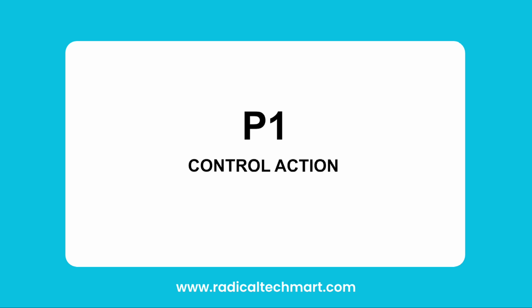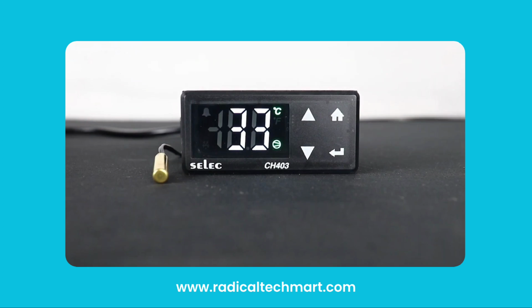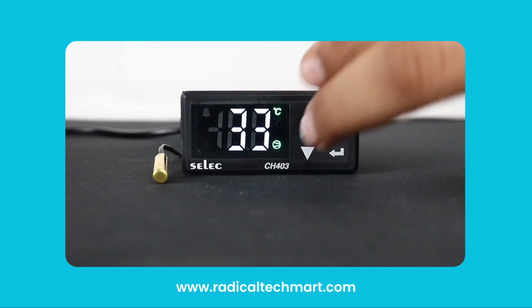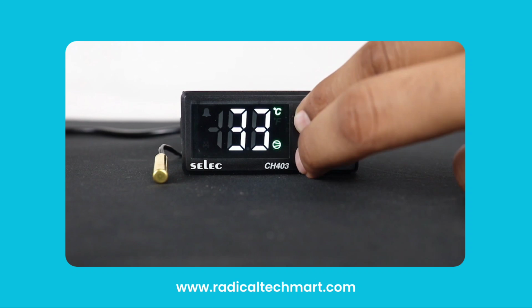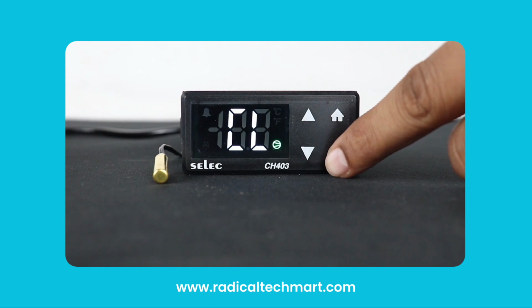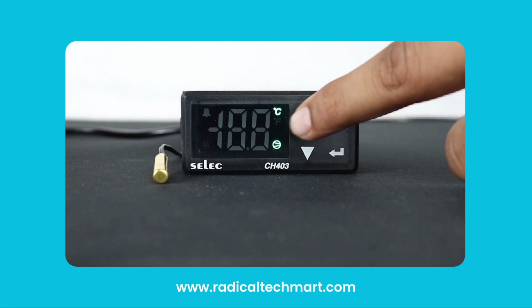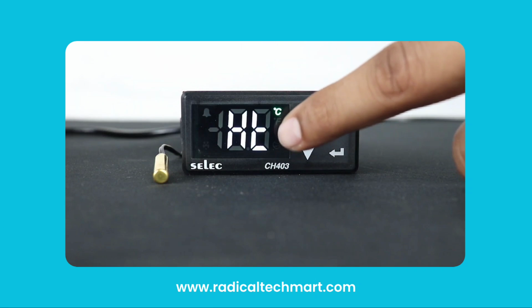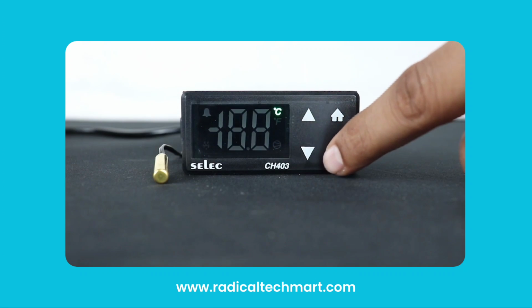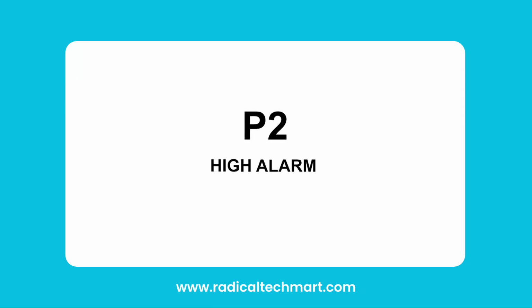To enter into the programming mode, we need to press the up and down keys for approximately 3 seconds. By doing this, we will get P1 on the display, which stands for the controlling action of the controller. The user can get the required action by either going for cooling or heating. To save the control mode, press the Enter key once.